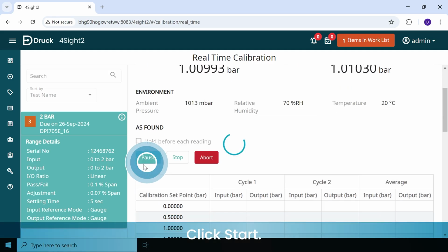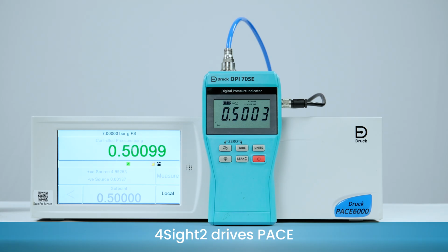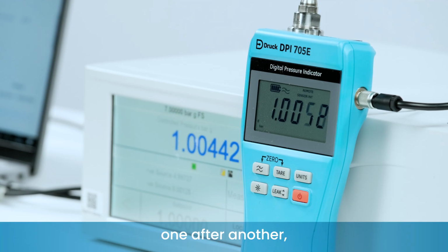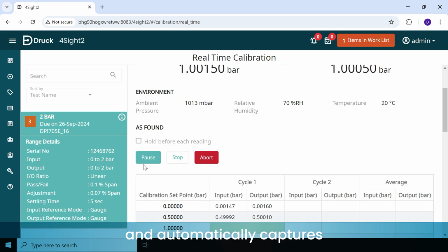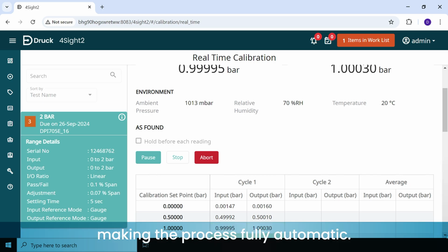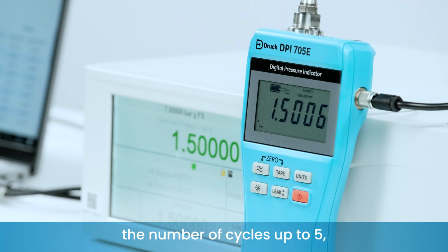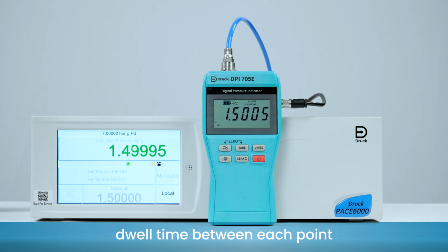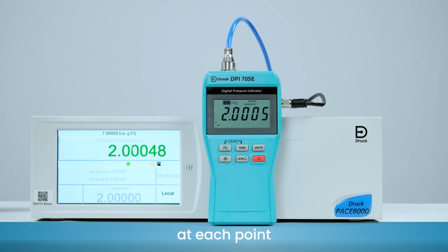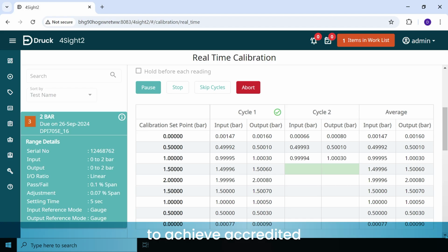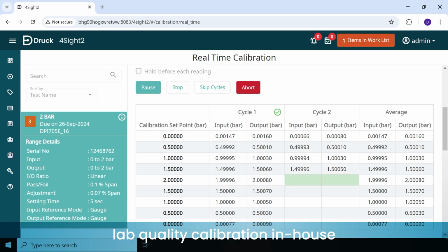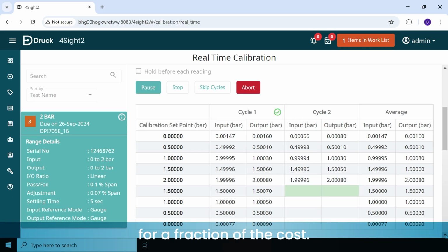Click Start. 4Sight2 drives PACE to control to every set point in the calibration procedure, one after another, and automatically captures the readings from the DPI705E, making the process fully automatic. You can configure the number of cycles up to 5, dwell time between each point, and also capture multiple readings at each point and average the value to achieve accredited lab quality calibration in-house for a fraction of the cost.